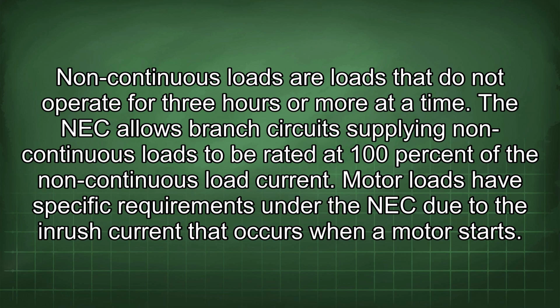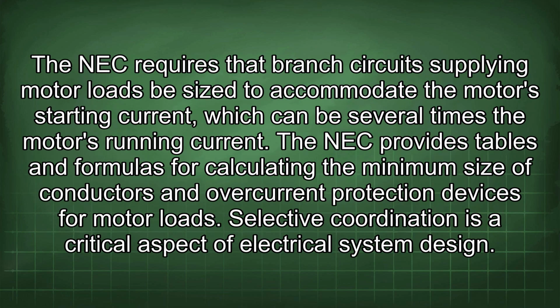Motor loads have specific requirements under the NEC due to the inrush current that occurs when a motor starts. The NEC requires that branch circuits supplying motor loads be sized to accommodate the motor's starting current, which can be several times the motor's running current. The NEC provides tables and formulas for calculating the minimum size of conductors and overcurrent protection devices for motor loads.